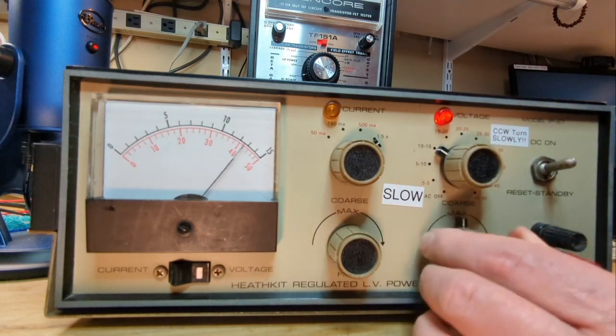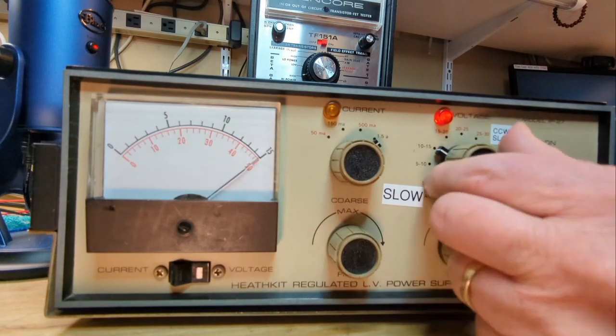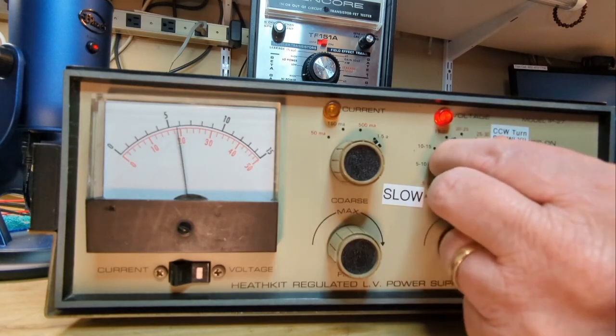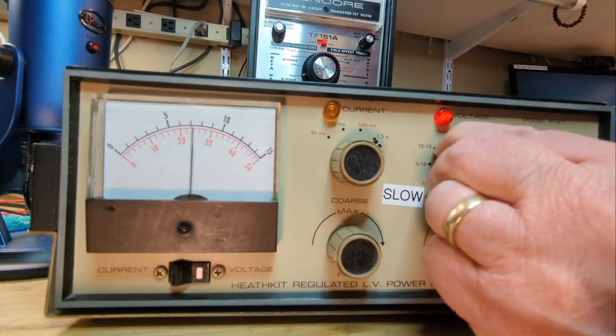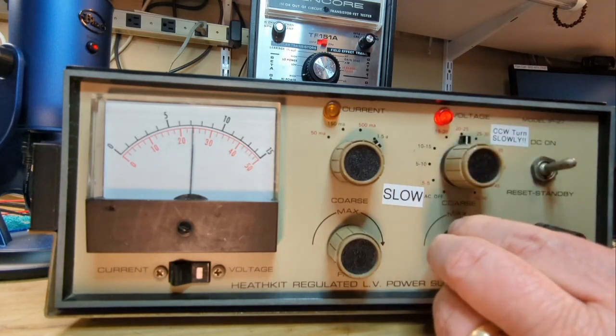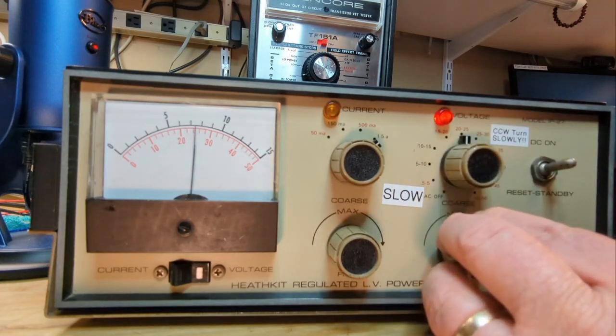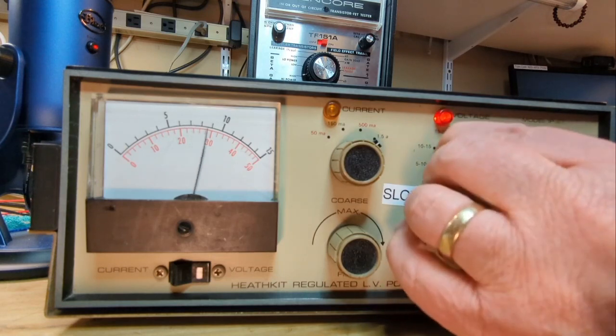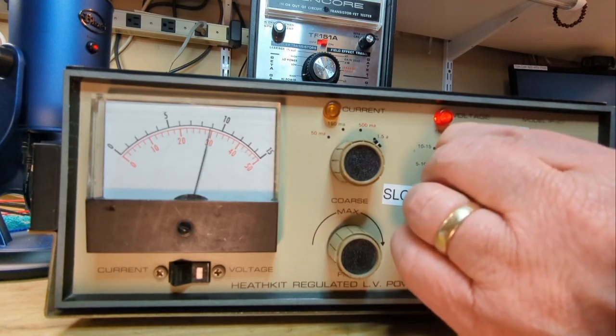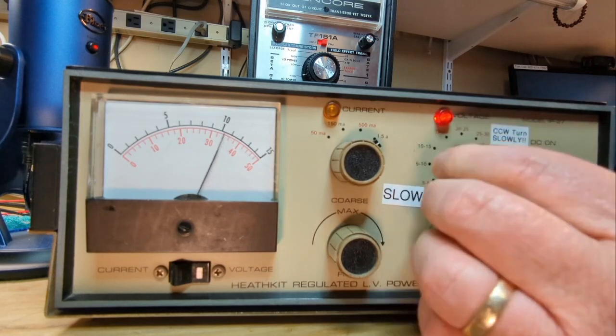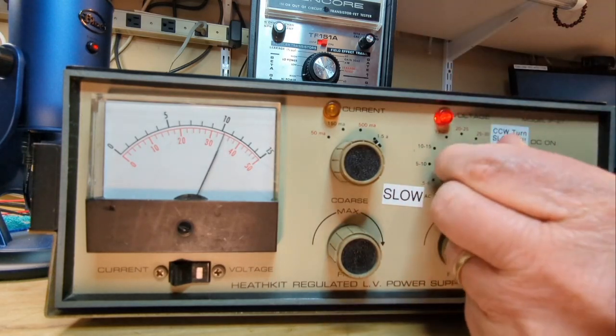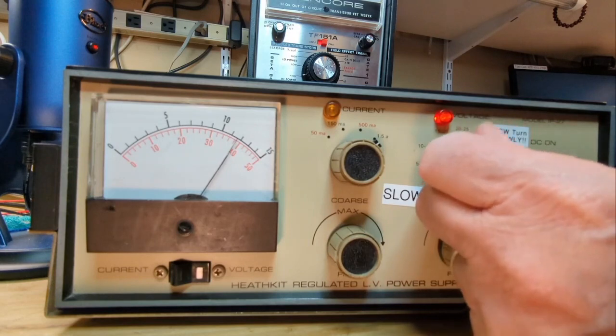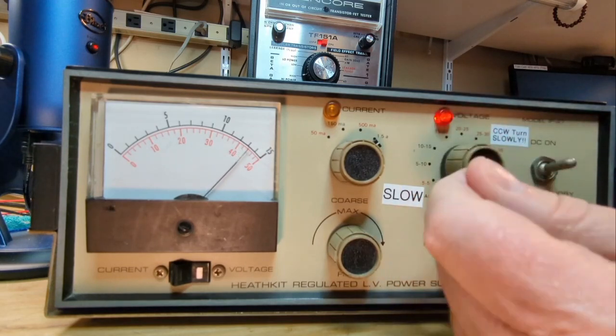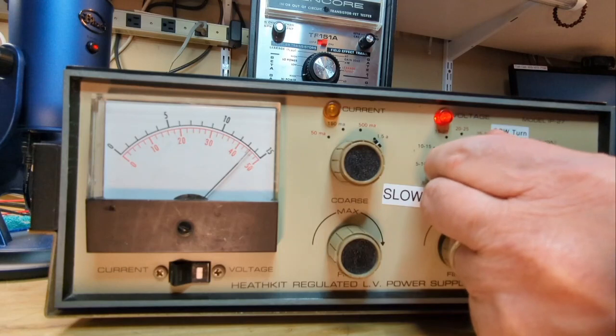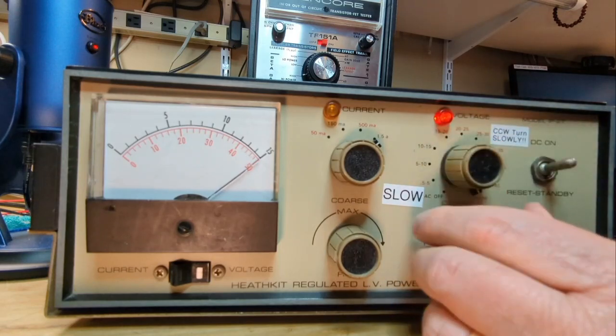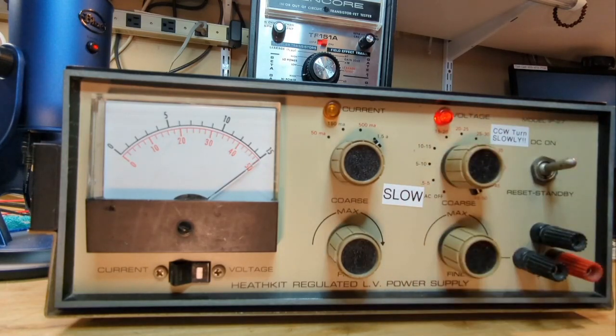I'm going to crank this up all the way. 15 volts. 20 goes to the red scale. It's on 20. 25 stays on the red scale, and it's pretty close to 25. There we go. 25 to 30 should take us to 30. 30 to 35 should take us to 35. It shows 34. Let me explain about that in a minute. 35 to 40. 40 to 45, and then 45 to 50. Brilliant. So all the voltage range works.